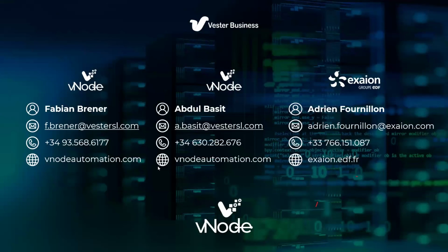Very good question. Configuration can be created using templates. If you have repeated connections, tags, folders, or devices, you can create a template and then create instances of that template, which makes configuration extremely easy. You just say, okay, all these connections go to this PLC—I have 100 like this, but with different IPs: number 1, number 2, number 3, number 4—and just change the IPs. You can have the same tags, connections, PLCs, or data diode connections repeated 100 times. You create templates for that and then create instances.